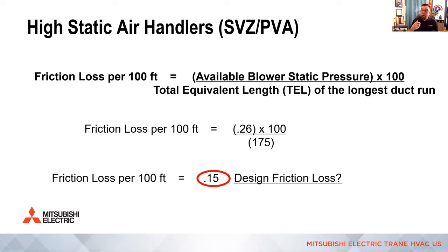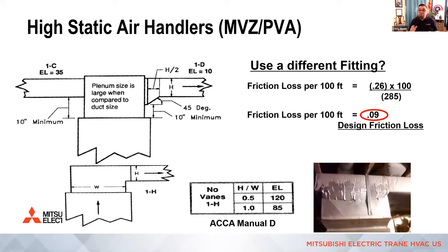And this is where customers, especially on a new duct system, if we're not designing using the right friction loss, people can get in trouble with higher static air handlers because it's gonna ramp up in order to deliver the volume of air that we need. And when it ramps up, the static pressure goes up, the velocity goes up. And that's when we start to get complaints, okay? So just because you see bad fittings doesn't mean the system wasn't designed around a bad fitting.